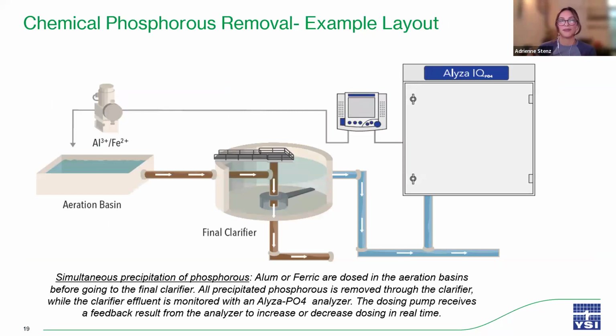So this is what an automated chemical removal system looks like. Some systems may have different or multiple dosing points, but we will look at this particular application called simultaneous precipitation. Simultaneous precipitation begins by dosing your alum or ferric at the end of your aeration basins, which with enough mixing will bind to as much phosphorus as possible. The water then moves on to a secondary clarifier in which those solids are settled out, taking phosphorus with it. The clean water then moves on to effluent treatment, which we can place an orthophosphate analyzer in to measure orthophosphate and provide a feedback signal back to our pump, which is dosing chemicals in our aeration basin.